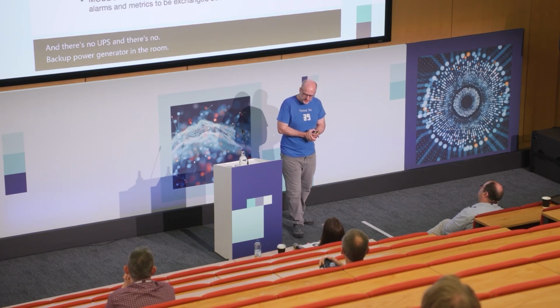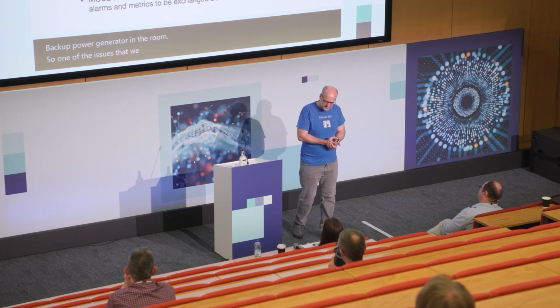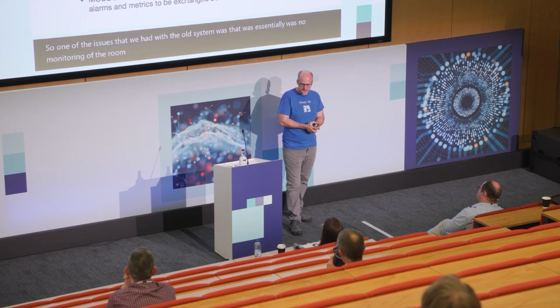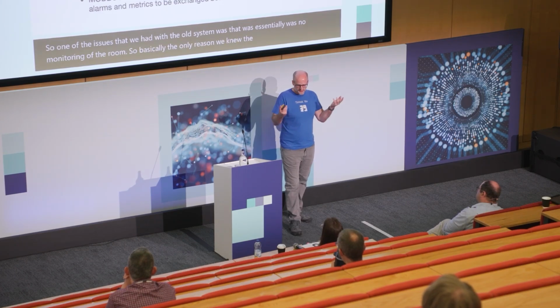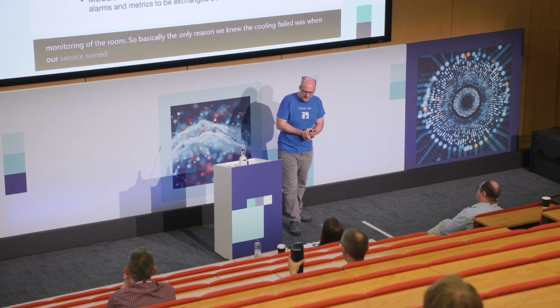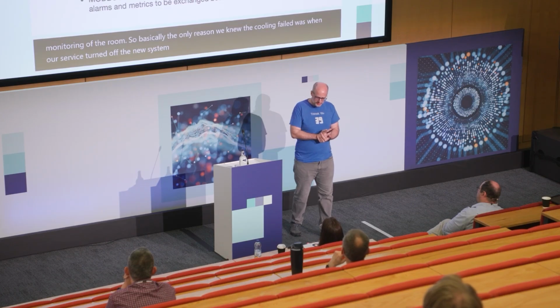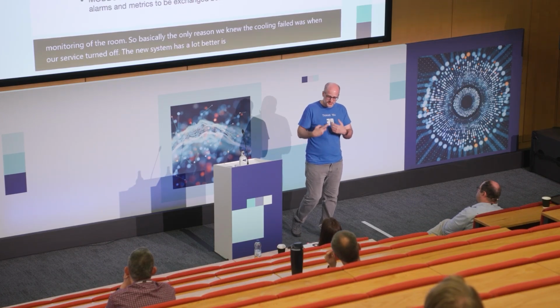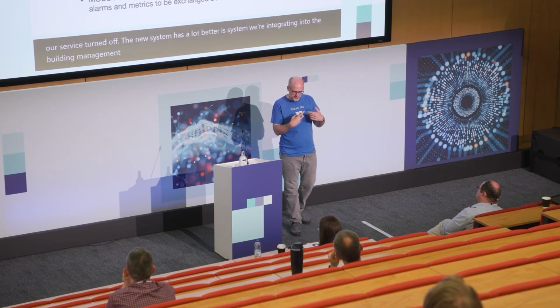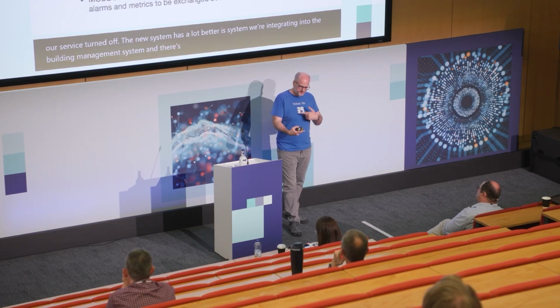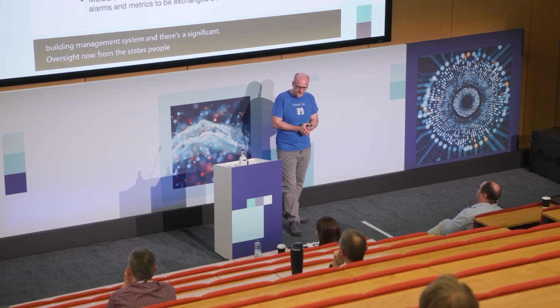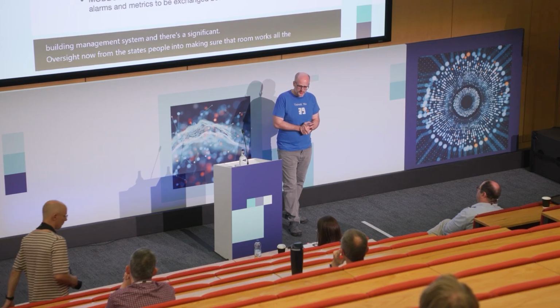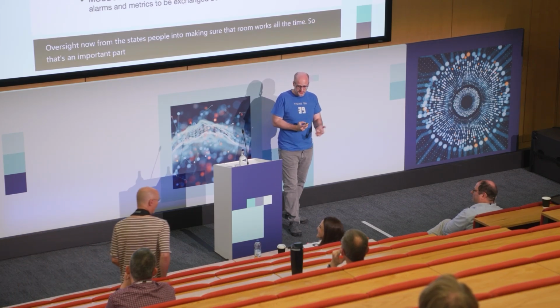One of the issues that we had with the old system was that there was essentially no monitoring of the room. So basically, the only reason we knew the cooling failed was when our servers turned off. The new system has a lot better monitoring. We're integrating into the building management system, and there's significant oversight now from the estates people into making sure that room works all the time. So that's an important part that has improved the resilience of the room. But as I said, there are a few future concerns.